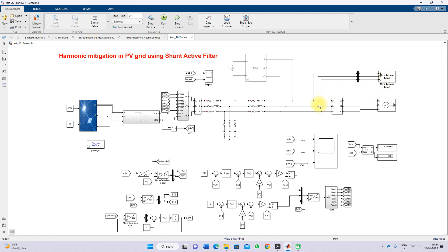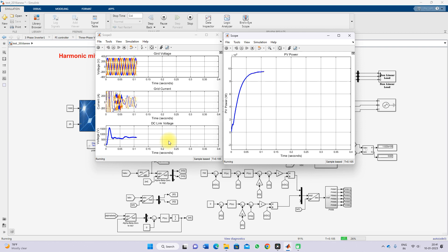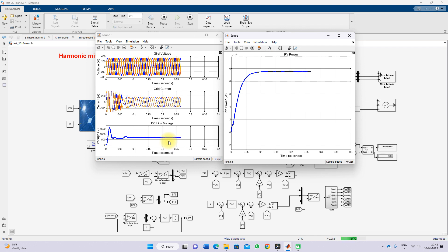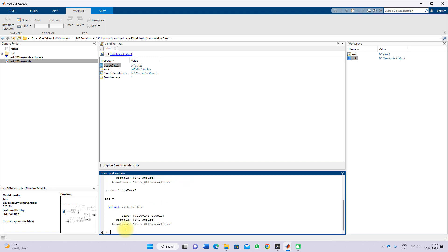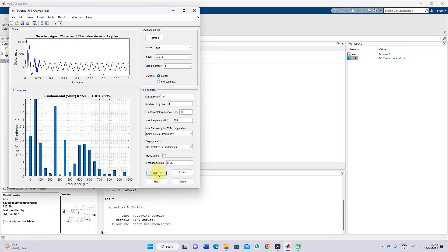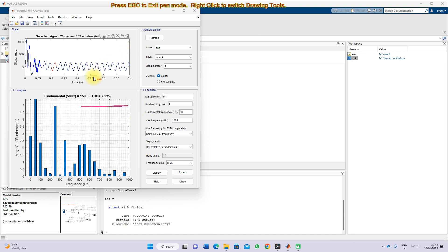Now I am adding the non-linear load and simulating the system. We get the same PV power, grid voltage, and DC link voltage, but there is distortion in the grid current because we have added the non-linear load. Because of the non-linear load, it draws reactive power from the grid, making the grid current non-sinusoidal. Refreshing the FFT analysis and checking the THD of the grid current after adding the non-linear load, we can see the THD is around 7.23%, which is more than 5% and does not comply with the IEEE standard.